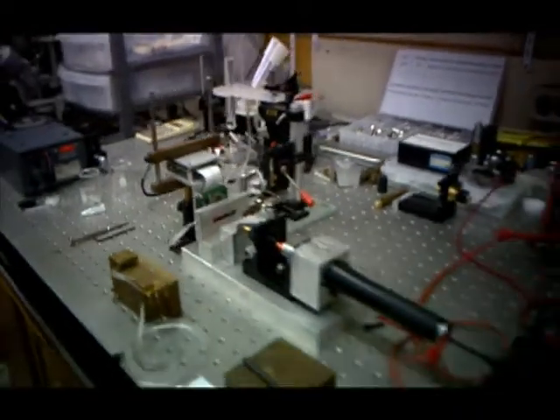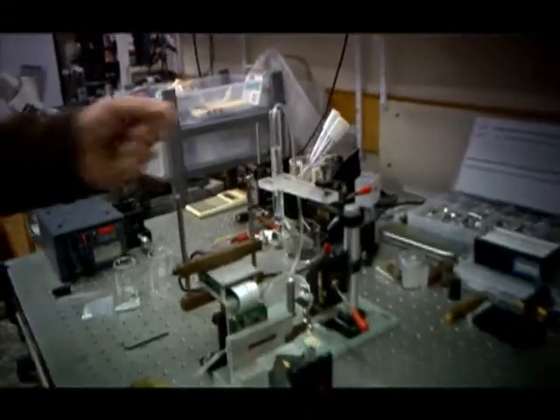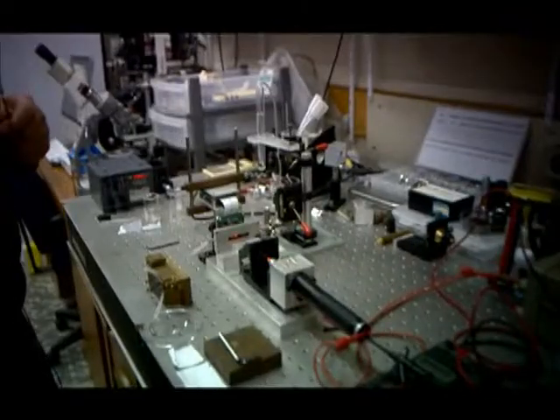We do digital inline holographic microscopy. It's a technology platform developed at Dalhousie University. We're developing a series of instruments to bring to market. This is our prototype for a flow cytometer to image particles that may be suspended in a liquid, which could be algae or bacteria. So you have a pinhole, just the light source and the screen, no lenses. And you get this incredible ability to image fairly large volumes, so cubic centimeters, with sub-micron resolution.